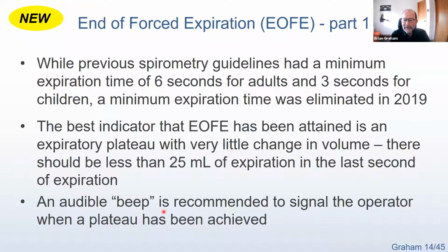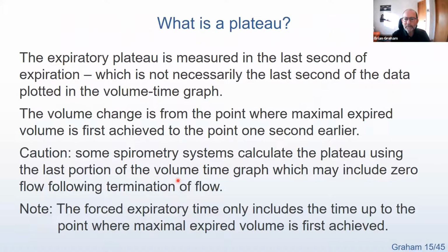Now, we've also recommended there should be an audible beep, for the system should give that signal to the operator when the plateau is reached. And the reason for this is that I've just seen far too many cases of the person who's the operator staring at the screen instead of looking at the patient. And they're staring at the screen because they're trying to figure out, is it 6 seconds? Did they reach a plateau? If you get that auditory beep, that gives you a better way of spending more time looking at the patient and then looking back to the screen. You've always got to be dividing your attention between the two, and that just helps.